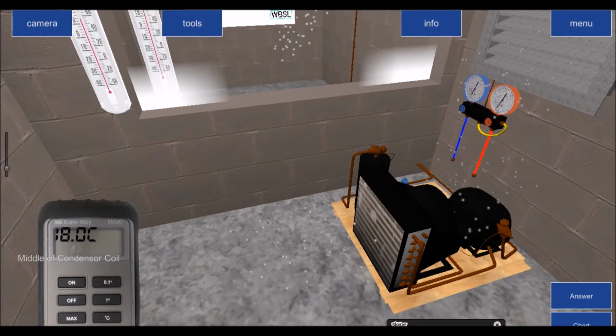So when I put my gauge in the middle of my condenser, anything between 30 to 40 degrees is within the norm. You might even find that it's on average about 15 degrees of a difference, so you might find that it'll be about 35 degrees Celsius condensing temperature. Then I know that that's the correct condensing temperature for the air temperature that's coming on, so for the ambient condition that the condenser is located in. So when the air temperature drops, so will condensing temperature. When the air temperature increases, so will condensing temperature.